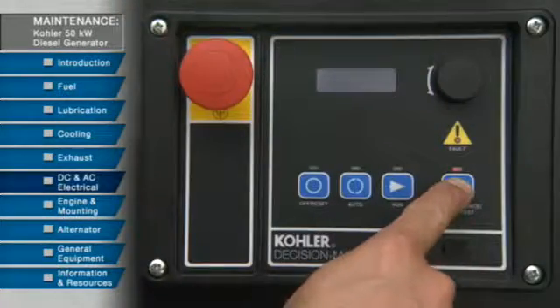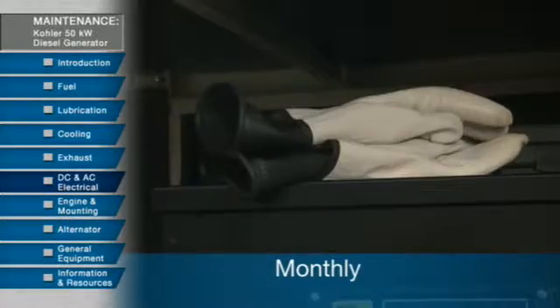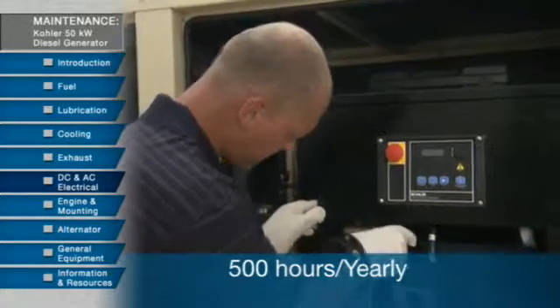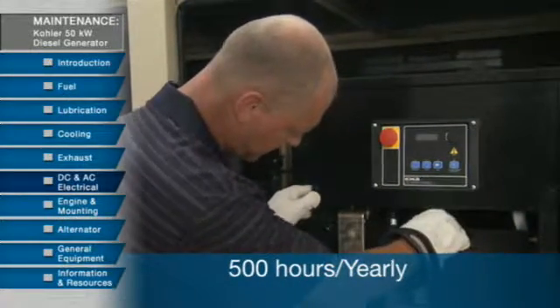When it comes to the AC electrical systems, every month you should test the controller display and do a general inspection. In areas subject to vibration or motion, note any wire abrasions. Finally, every 500 hours or yearly, go around and tighten the control and power wiring connections.